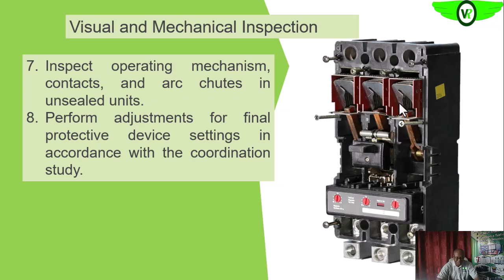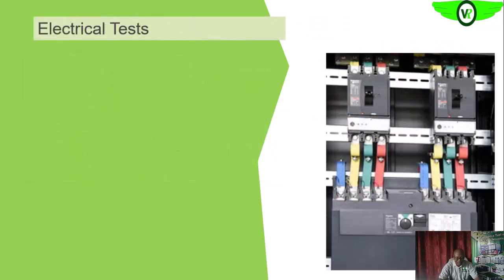So once we have done that, we can perform the necessary adjustment. And as we are performing the adjustment on this setting, we need to also take into consideration other breakers or other protective devices that are either upstream or downstream. So we want to coordinate this or set it in accordance with the coordination study and short circuit study of that particular installation.